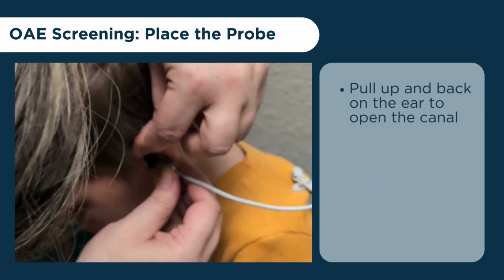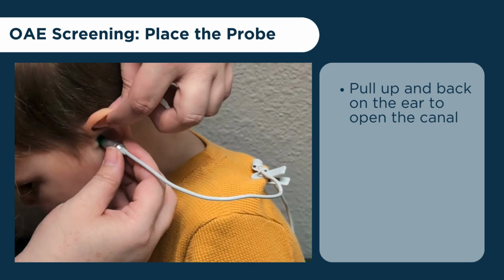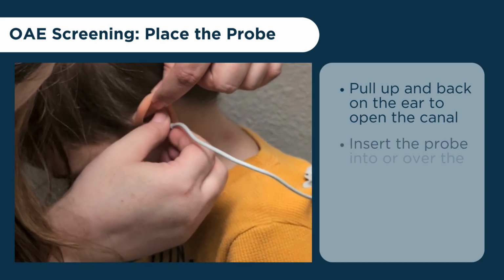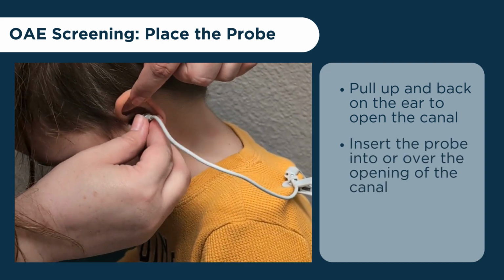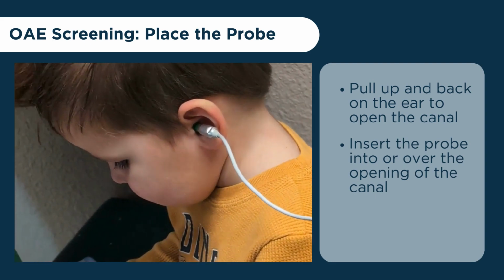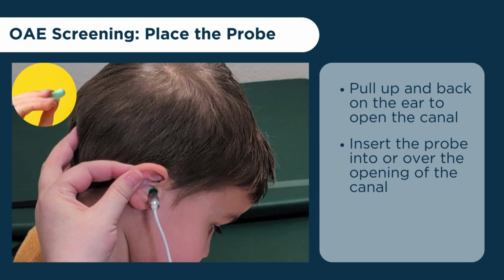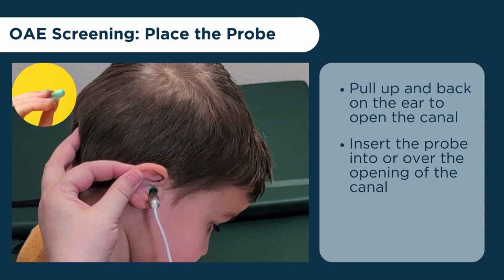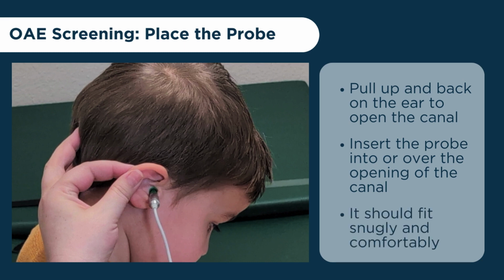With one hand, gently pull up and back on the outer ear to open the canal. With the other hand, gently insert the probe tip into the ear canal, angling it slightly forward and down toward the nose. If you're using a soft foam tip, roll it between your fingers to compress it before inserting it into the ear canal. Push it firmly into the canal with a slight twist. It should fit snugly and comfortably just inside the ear canal.